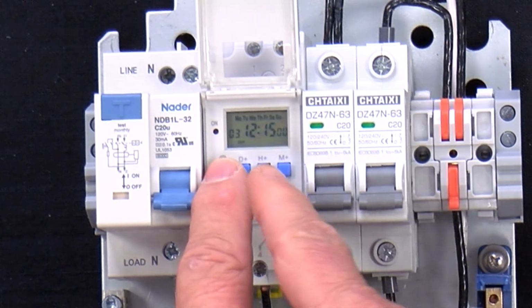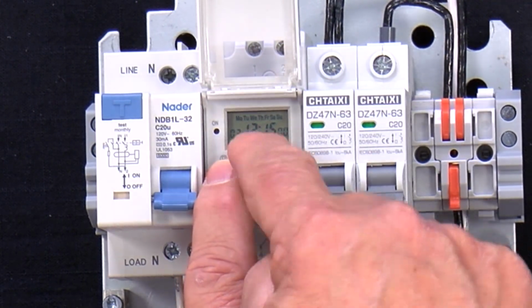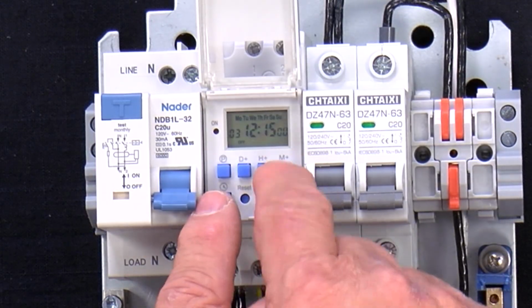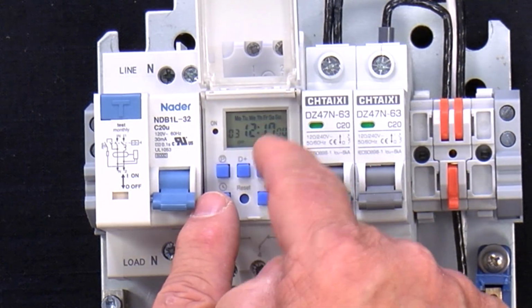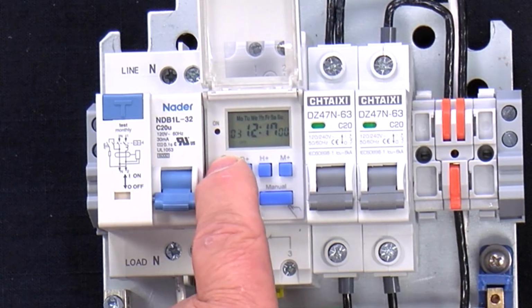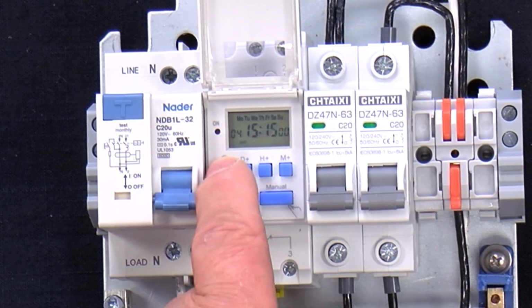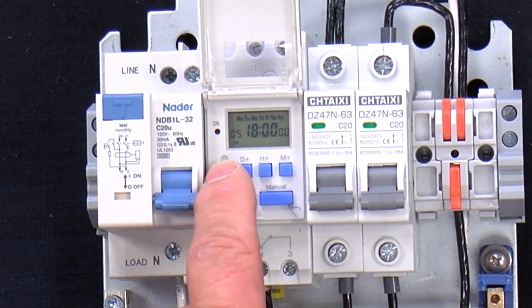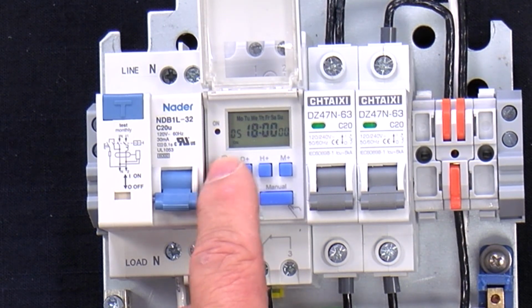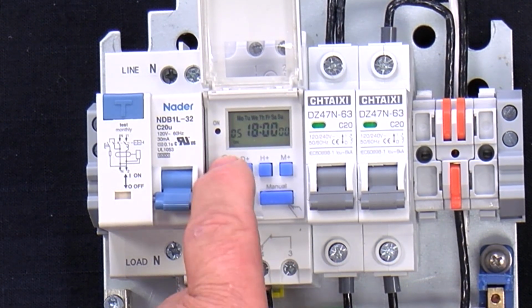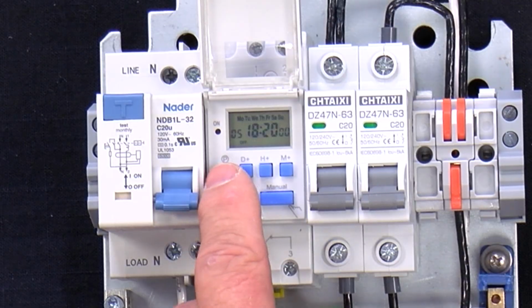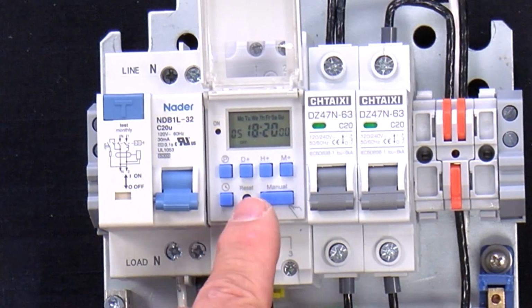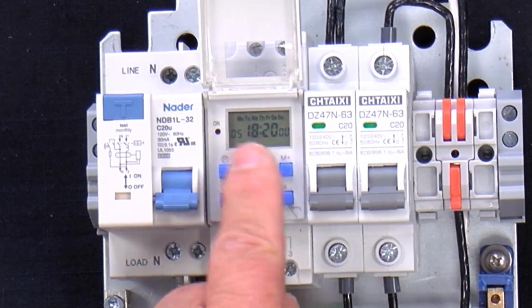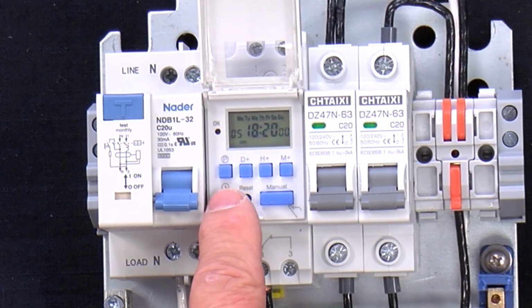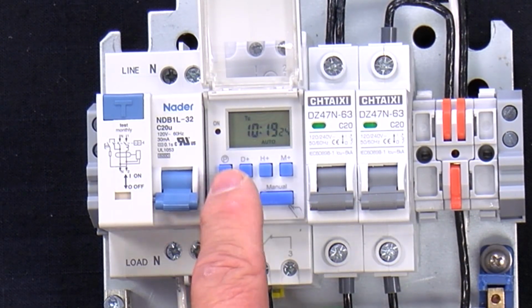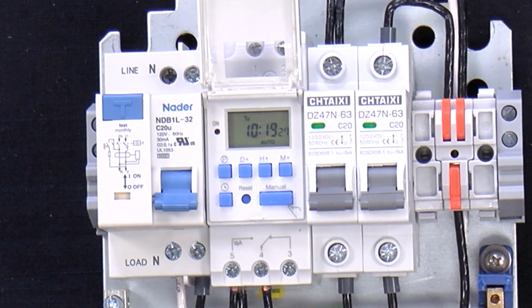Again, you can adjust this exactly the same way. Once you're in that programming mode, you don't have to hold the programming button, but you can add a couple minutes if you want to. At 3 o'clock to 3:15, and then 6 o'clock at night, notice it's in 24-hour time, to 6:20, and then it recycles off. To get out of the programming mode, you hit the clock button. It's very simple. And now you're back to 10:19.